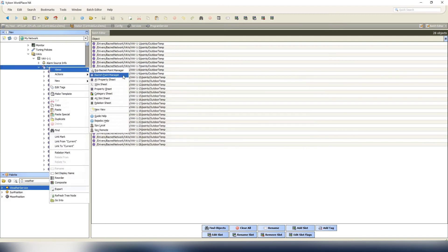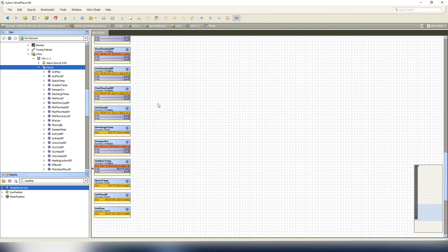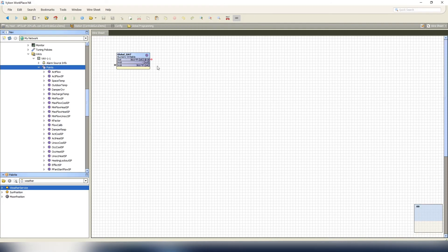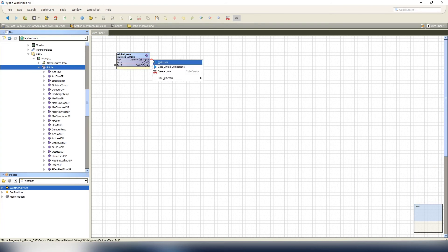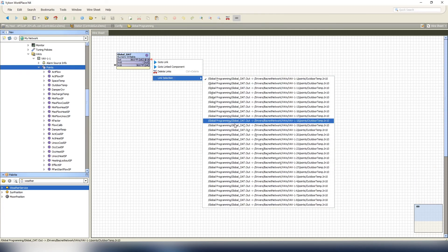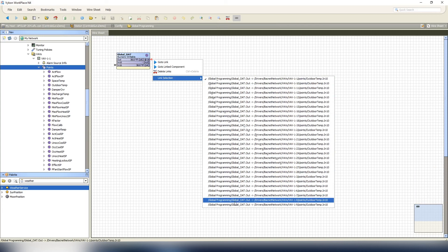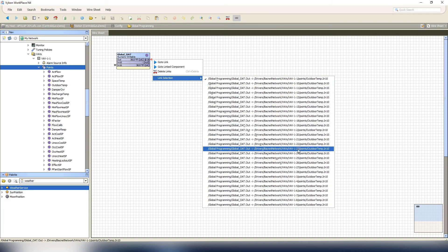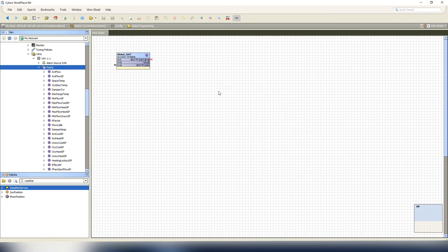Then we're gonna view the wire sheet once again. Find our outdoor air temp, and as you can see, it has been linked back to global outdoor air temp. And to show you the link selection, it shows you it's linked it to every single one of these points, VAVs across the board. And that's how you would link one point to multiple points through the program service.